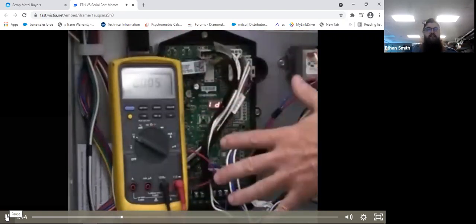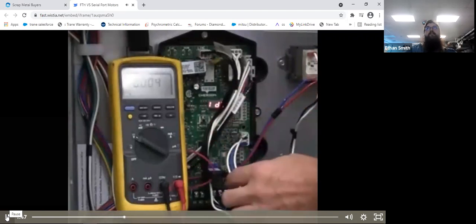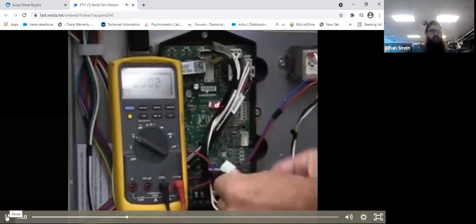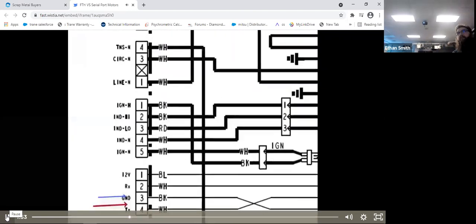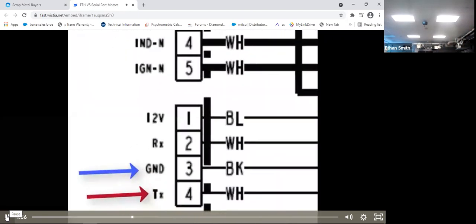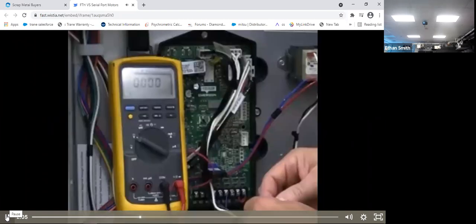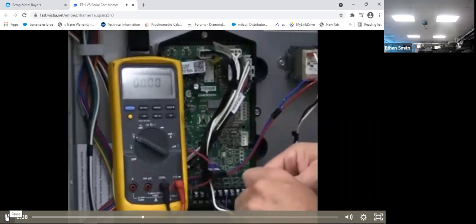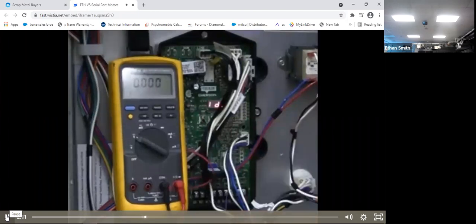Now the S furnace, the motor is behind the plate and the control board. So the easiest diagnostics on that is to ensure that I send 24 volt to transmit and ground, which duplicates what the wiring harness does. But here I can simply apply to the harness. So ground will go on the ground terminal for common, and I'll put 24 volts on the transmit, and my motor is going to run at 75% airflow. If my motor runs with a go no-go test, I need to continue with the troubleshooting process. If the motor does not energize when it has high voltage applied and 24 volts applied, and I follow the power cycle sequence for at least 60 seconds off, then I know that my motor has failed and I need to order a new motor module.